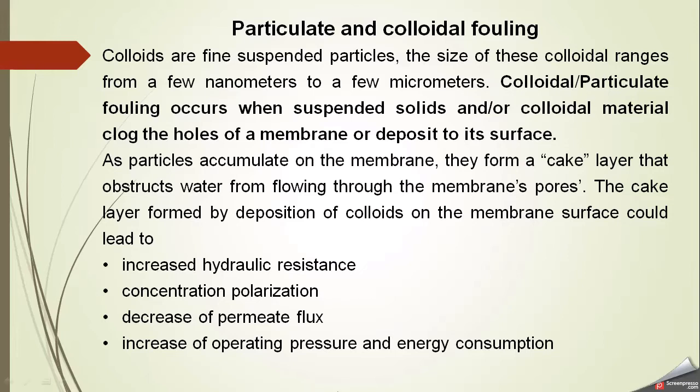The cake layer formed by deposition of colloids on the membrane surface leads to: increased hydraulic resistance; concentration polarization between the raw water and the permeate; decrease of permeate flux due to reduced available flow area; and increased operating pressure and energy, since transmembrane pressure increases when pores are blocked and more energy is needed to produce the same amount of water.